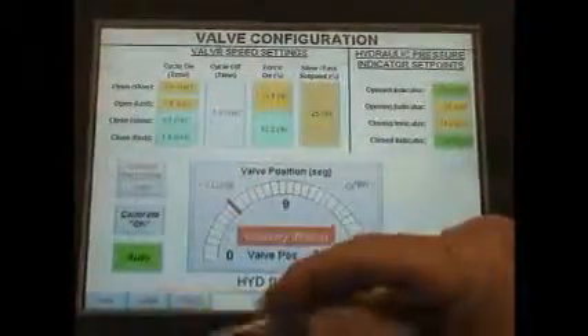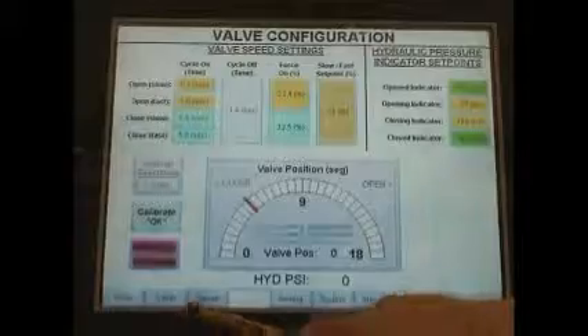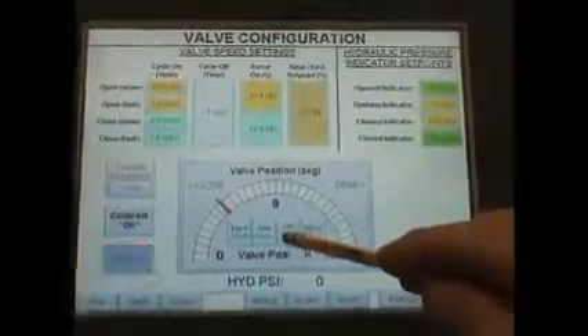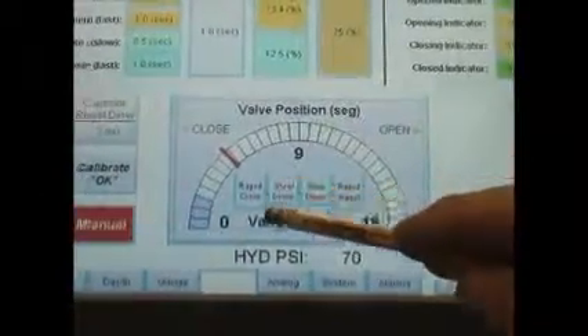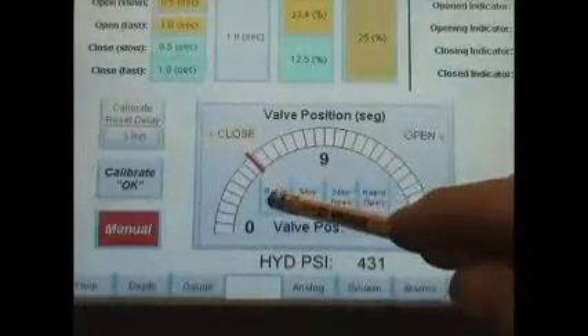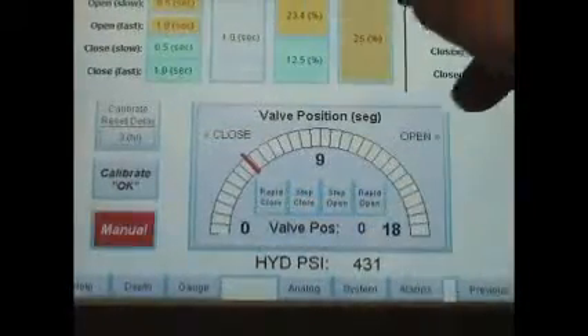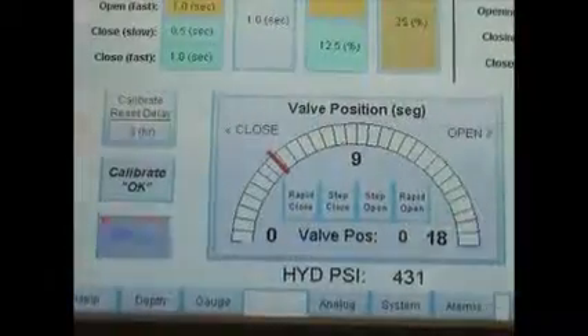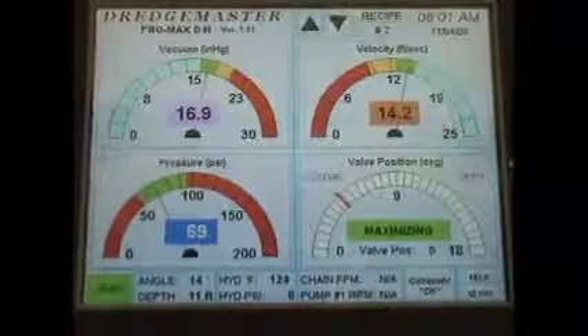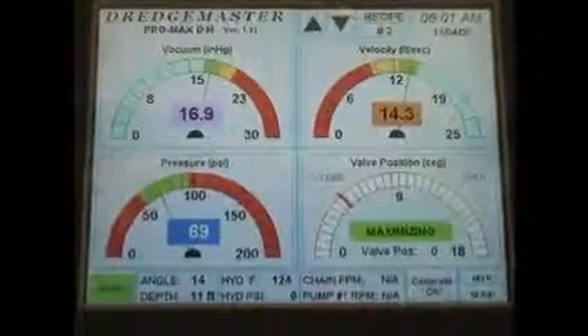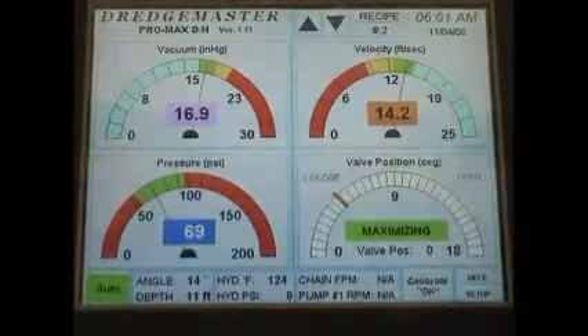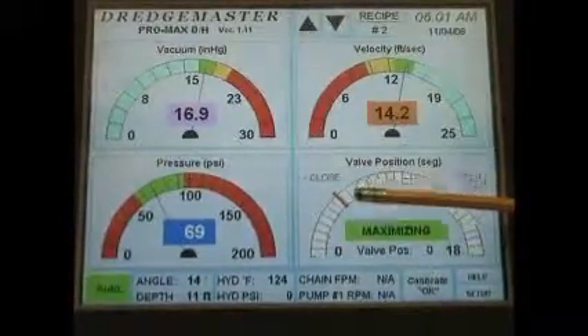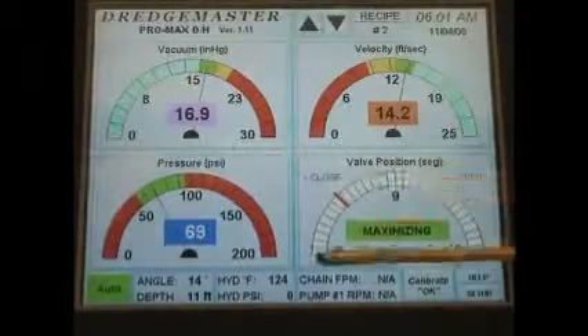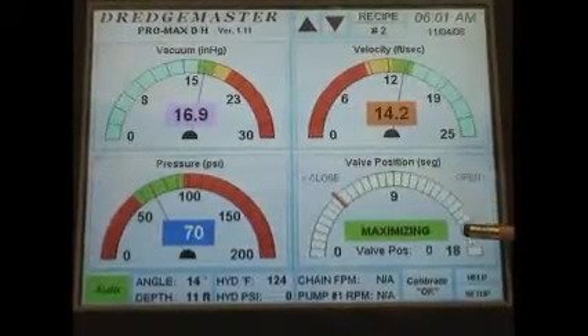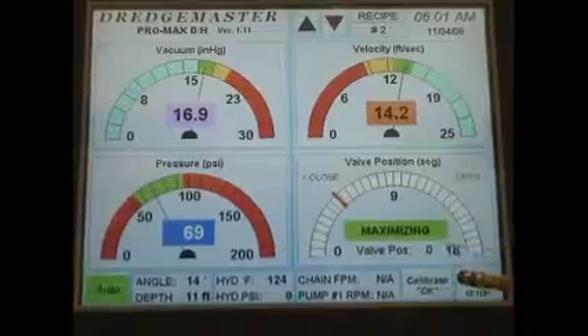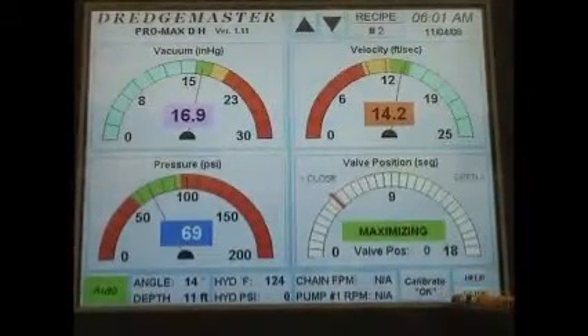From the valve configuration screen, you can also select manual, and you can step the valve open or step the valve closed, or rapidly open the valve or rapidly close the valve from the valve configuration screen. If for any reason the operator wants to calibrate the cylinder, he feels maybe the accuracy of the position is not accurate in relation to what the position of the cylinder is under the water, the operator can simply touch the calibration OK.